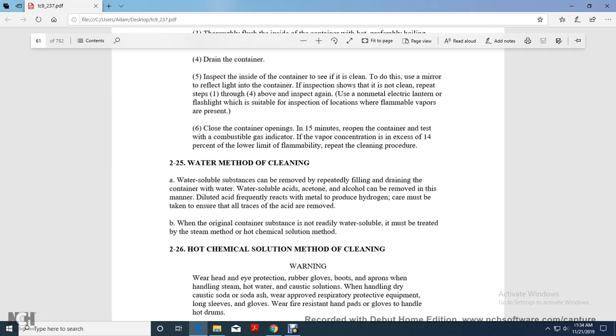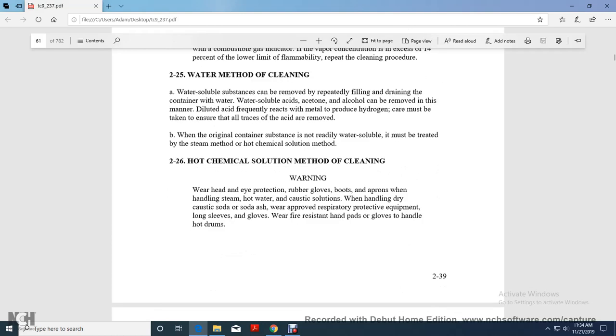Inspect again. Use a non-metal electrical lantern or flashlight suitable for the inspection location. If flammable vapors are present, close the container openings for 15 minutes. Reopen the container and test with the combustible gas indicator. If the vapor concentration is in excess of 14% of the lower flammable limit, repeat the cleaning procedure.